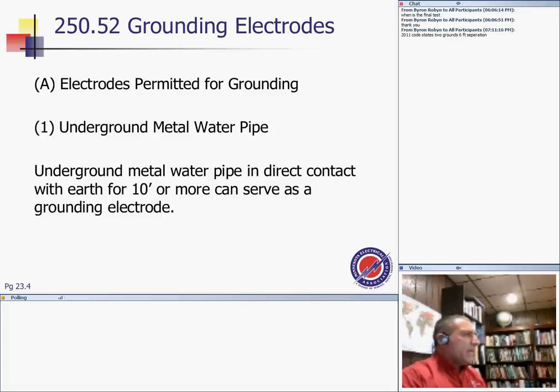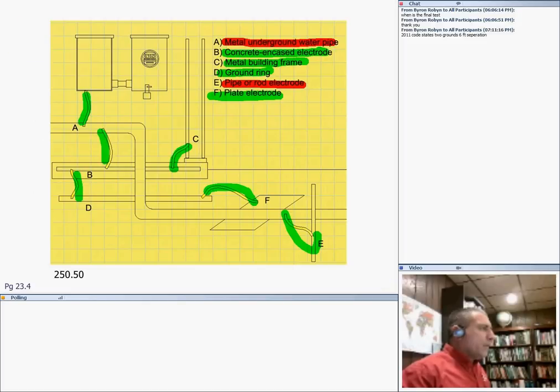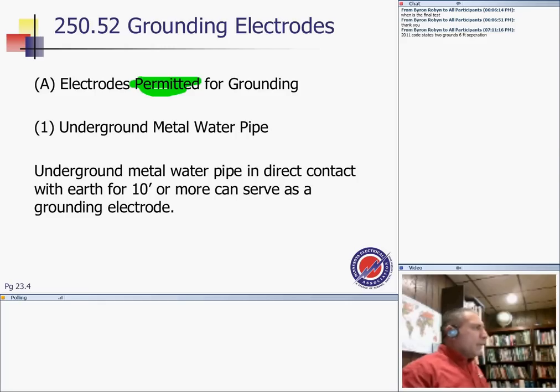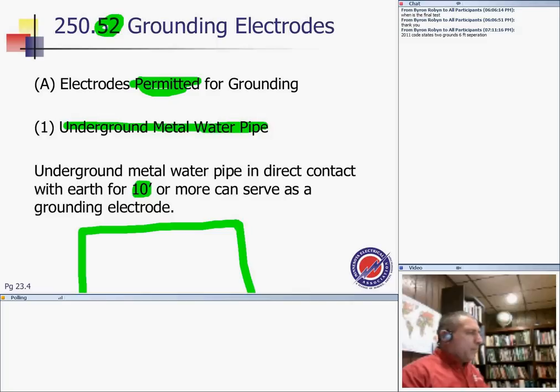Grounding electrodes permitted. There are permitted ones. We went through a bunch of them here. There's 1, 2, 3, 4, 5, 6 of them. You guys are looking at them right here. Underground water pipe, guys, and here are some restrictions, and you can find this directly in 250.52. If you have a water pipe, they want it to be in direct contact with earth for 10 feet or more. It has to be in direct contact with Mother Earth for 10 feet before you use it.